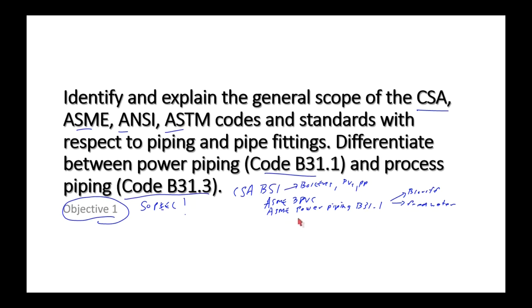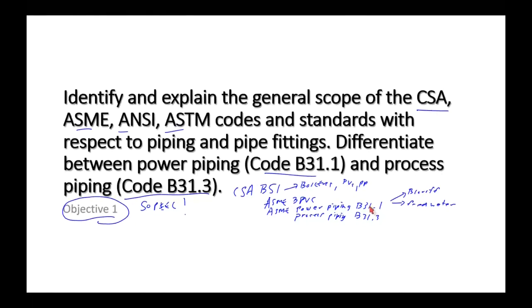There's also the ASME Process Piping Code, B31.3. All pressure piping codes start with the letter B and they're all 31-point-something — for example, B31.5 is refrigeration piping. This is all part of the pressure piping code; it is not the same as the boiler or pressure vessel code.